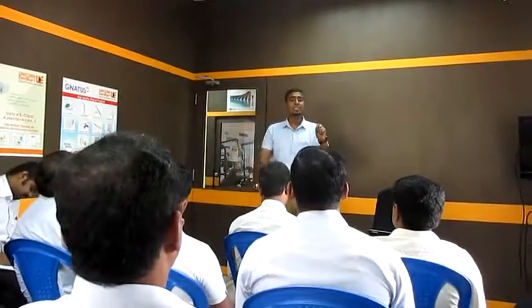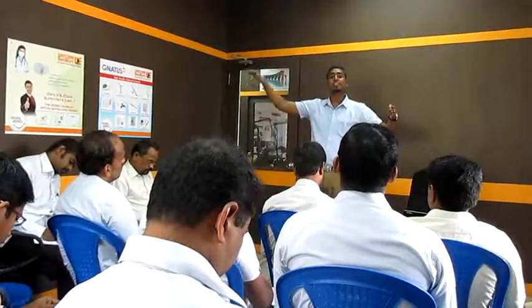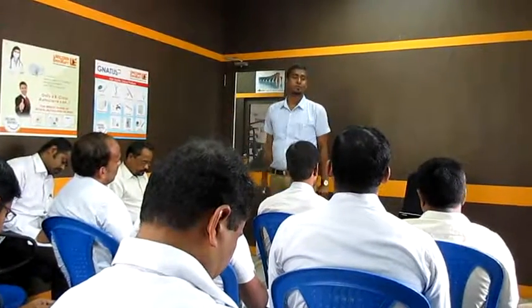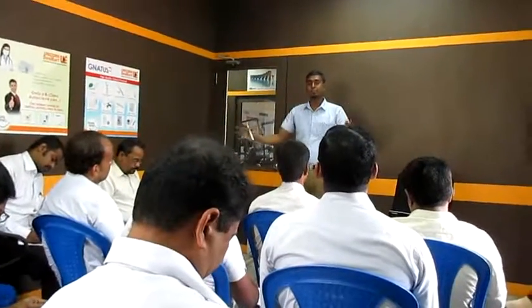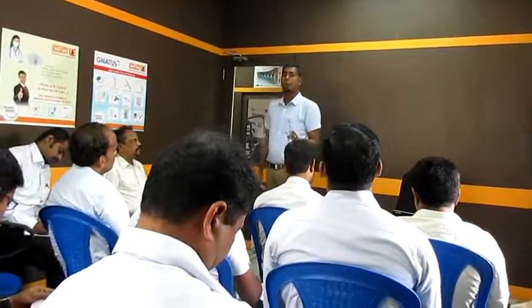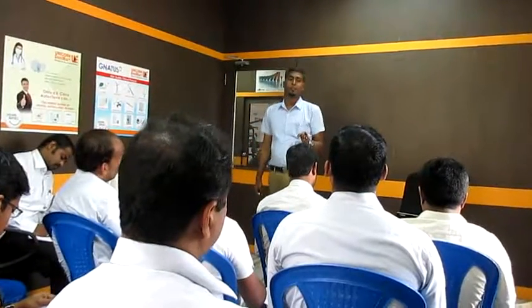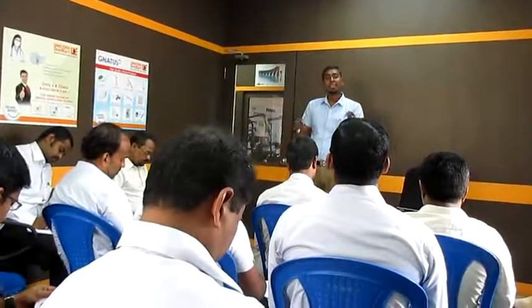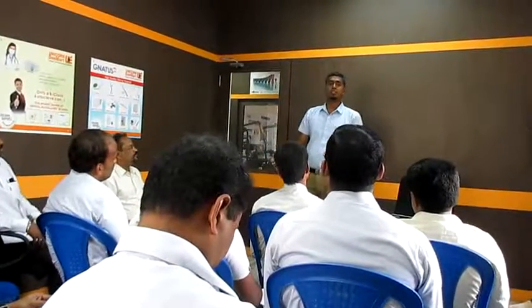It means if a machine is set at 70 kVp, anywhere from 65 up to 75 is allowed. More than plus or minus 5 is not allowed. Like that, they have deviation limits for all 5 parameters.